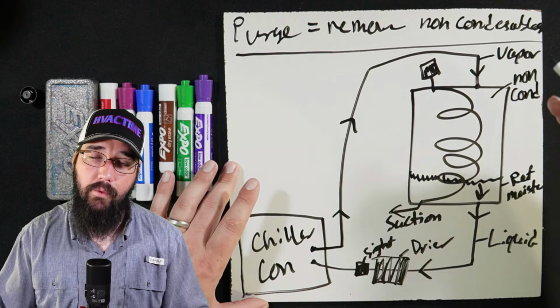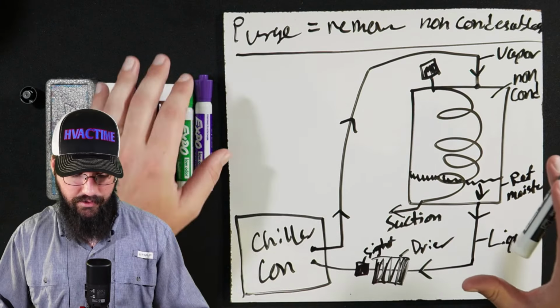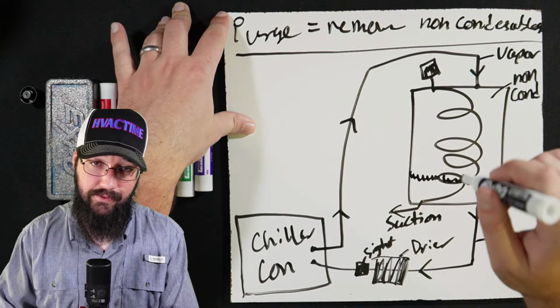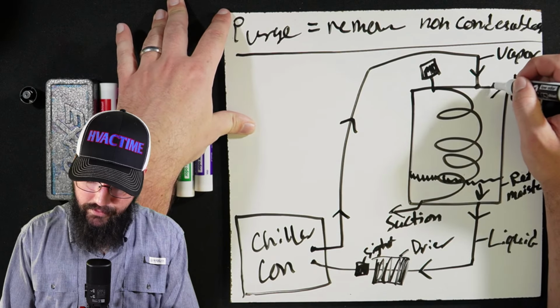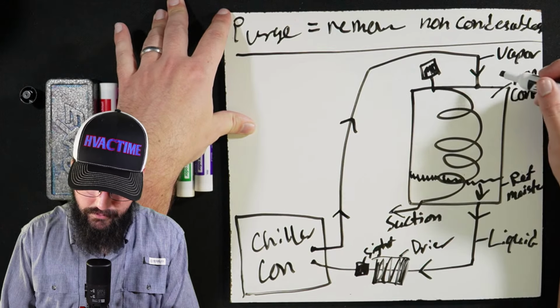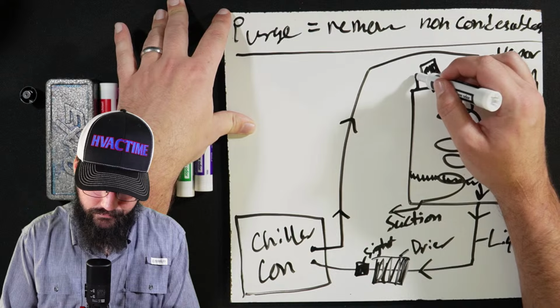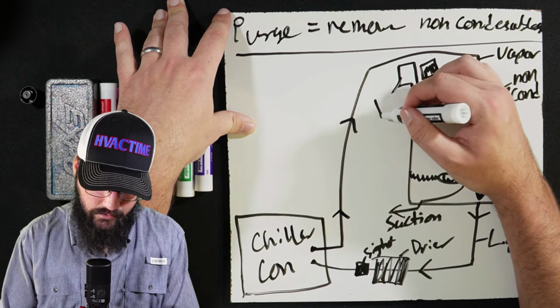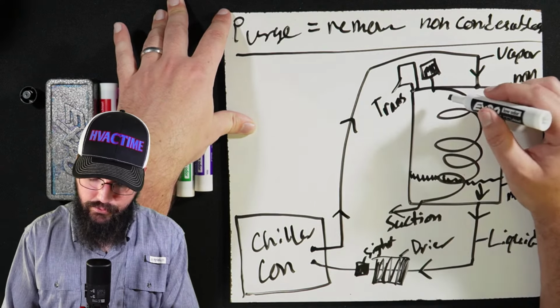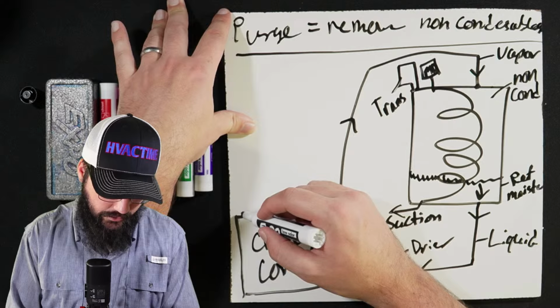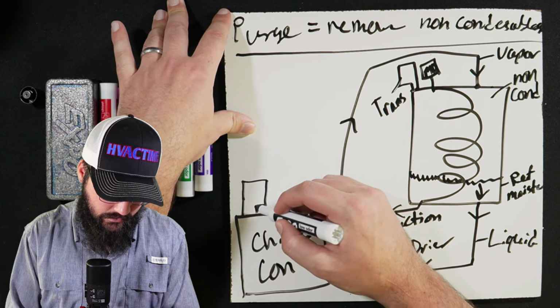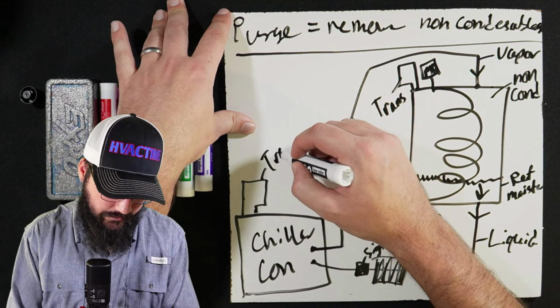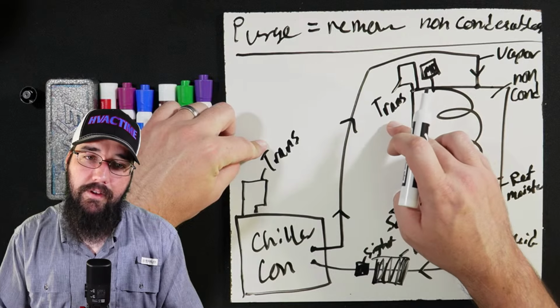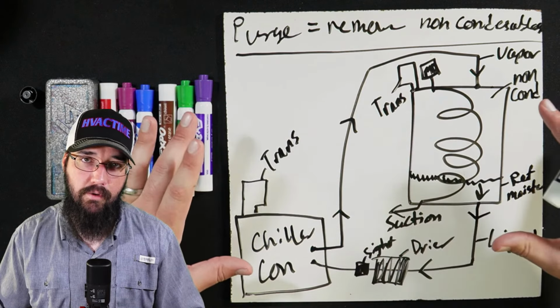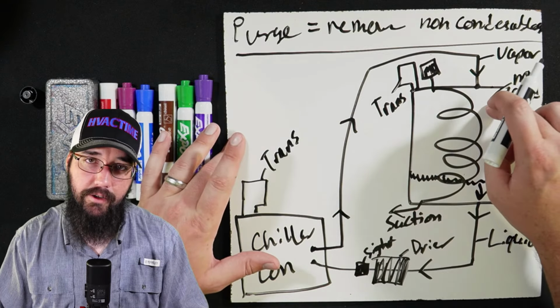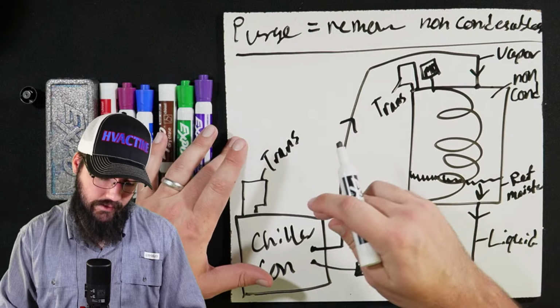Now, Trane does it one way, York does it different. Everybody has a slightly different version of this. How York is doing this specifically, they have a transducer. I don't want to clog up our... we'll put it over here. So they have a transducer monitoring pressure on this chamber. And then they're comparing that transducer to the condenser transducer. Essentially, when these pressures start to get too far apart, the differential, this purge pressure transducer will show a higher pressure than the condenser pressure transducer.